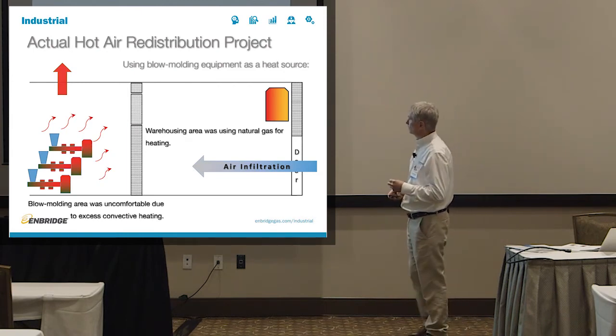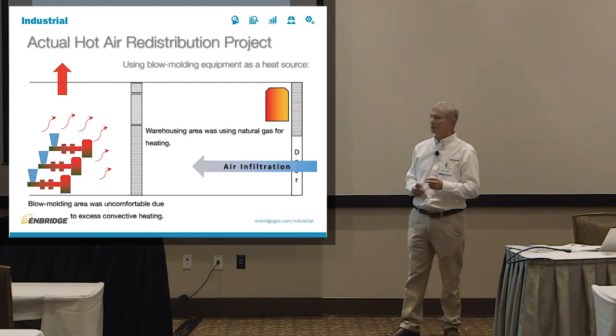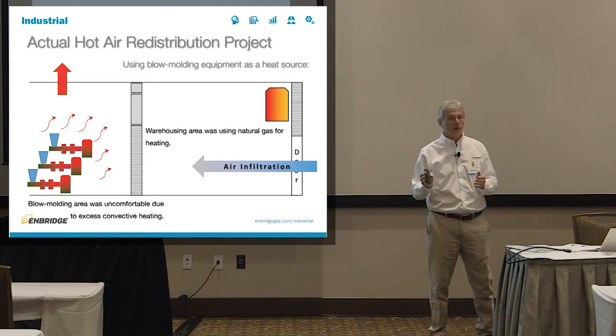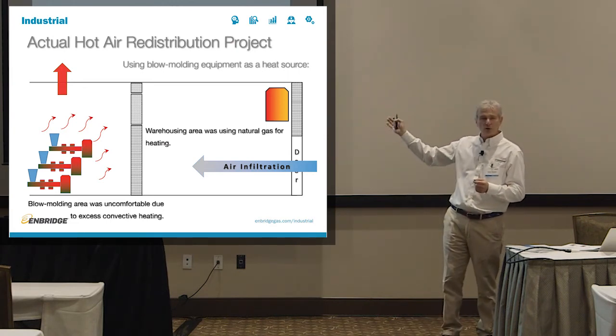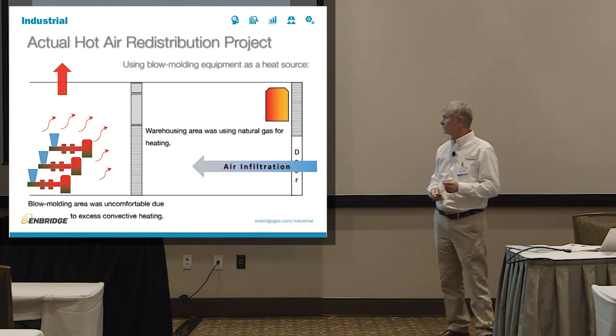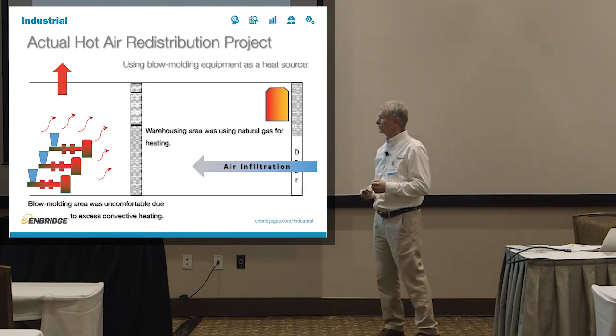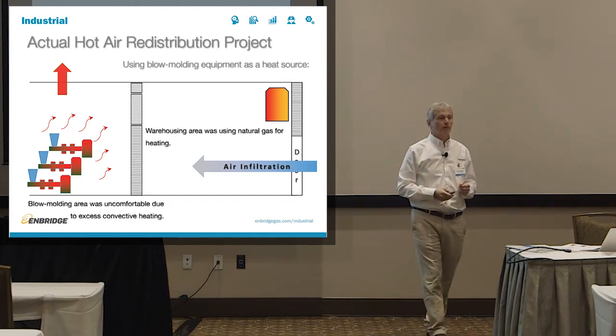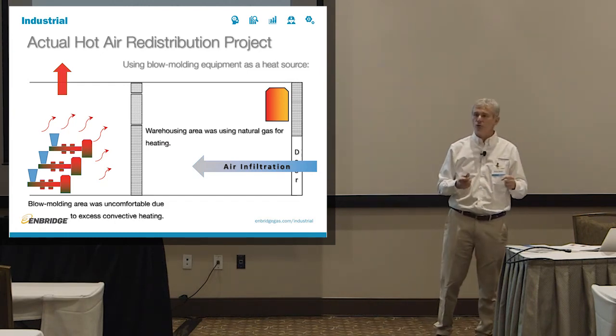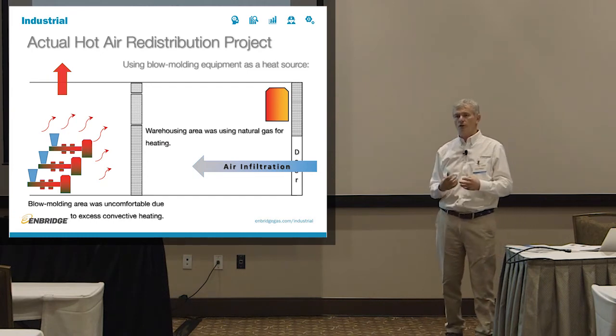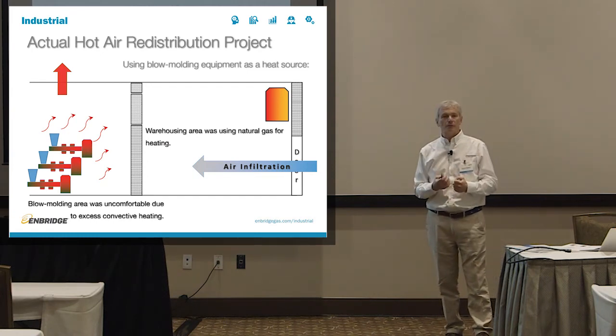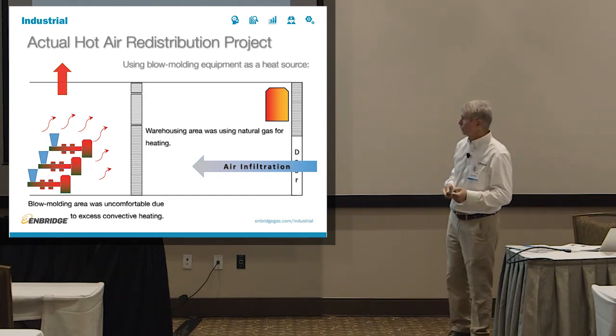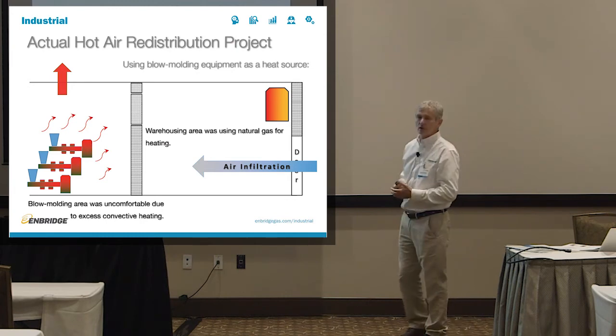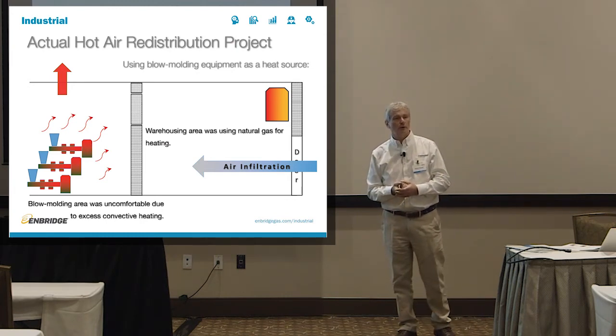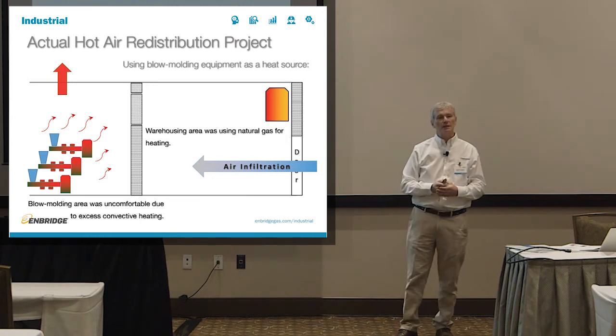So here's an example. Warehousing area. It was heated using natural gas. Through the shipping doors, we had all sorts of air infiltration in the wintertime. On the other side of the wall, we had a bunch of extrusion equipment. And what does extrusion equipment do? For those of you who know plastic equipment, it generates a lot of heat. So it was very uncomfortable because you're constantly hot, especially in the summertime. So to solve that, of course, these people have a bunch of exhaust on the roof. Well, these people use natural gas to heat the warehouse.